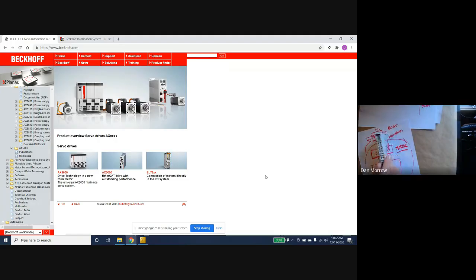Here on my cam, I've got a slice out. If you haven't seen a slice, this is what they look like. On the top side, push wires, there's a specialty screwdriver. Roger can show you, or one of the guys can show you, there's a screwdriver that goes in there that releases a little spring clip, LEDs on the top side. There's the release mechanism for the DIN rail, and when I pull on it, you'll see it's flattening that out so it releases it off the rail, and then it literally just slides up off the other units.